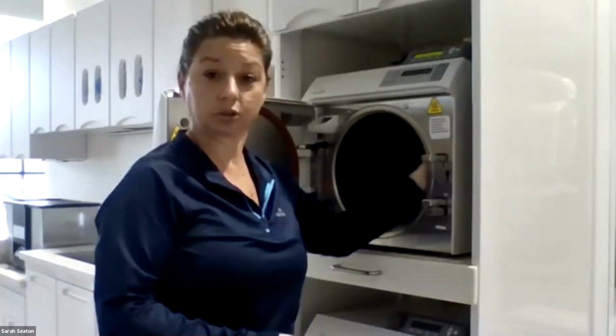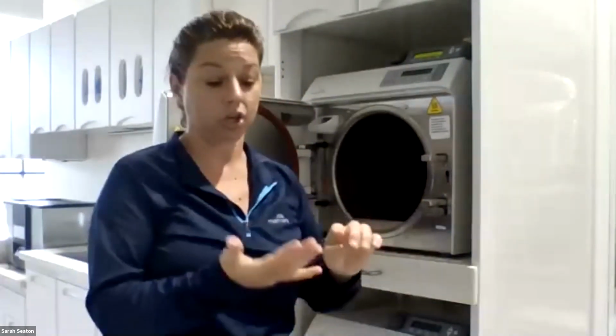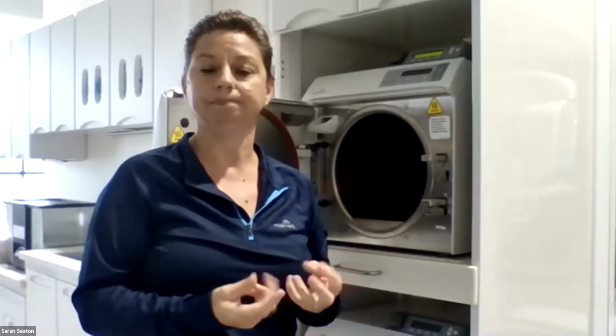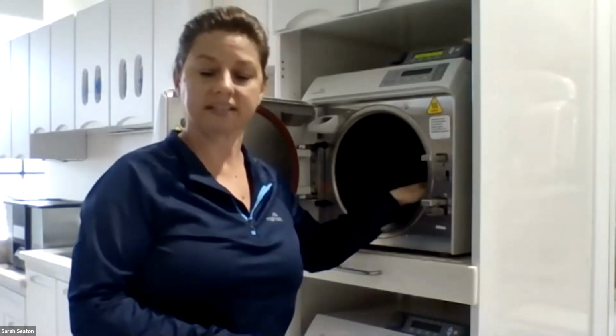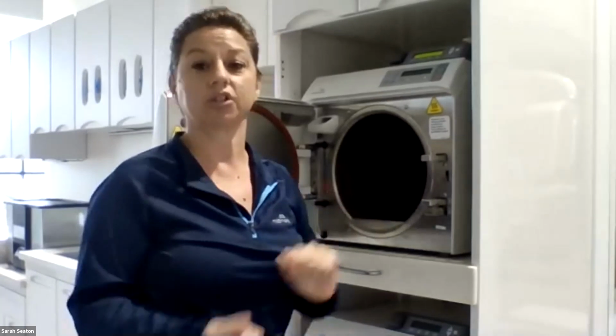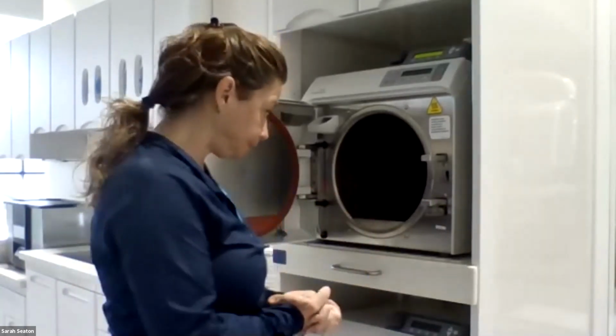Now, once you have that out, you can clean your internal surfaces of your sterilizer. You will want to clean your tray plate, your racking, and your trays. You'll want to use a speed clean and distilled water solution. And then you'll want to rinse that off and dry it prior to reinstalling those trays, tray plate, racking.